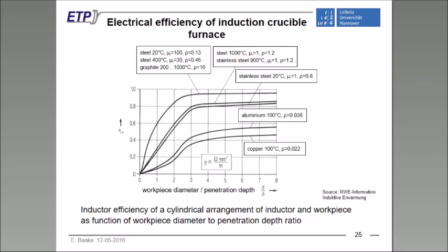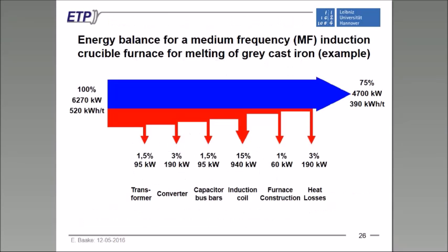And that's the second reason why medium frequency furnaces, several hundred hertz, are used today instead of line frequencies: in order to get a higher efficiency when we want to melt very small size scrap, when we want to start with the empty furnace filled up with small size scrap and use the so-called batch process, not the process with the heel which was used in former times. This is the second reason for this.